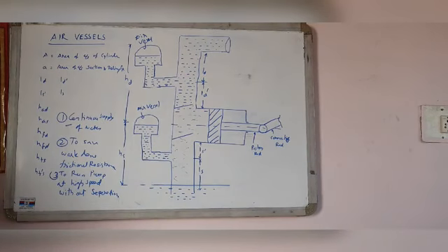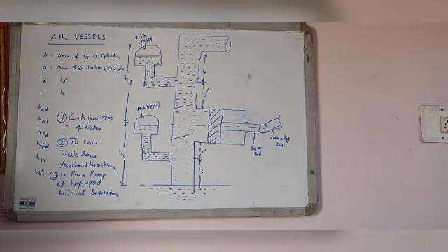During the first half of the suction stroke, the piston moves with acceleration, which means the velocity of water in the suction pipe is more than the mean velocity, and hence the discharge of water entering the cylinder will be more than the mean discharge. This excess quantity of water will be supplied from the air vessel to the cylinder in such a way that the velocity in the suction pipe below the air vessel is equal to the mean velocity of flow.